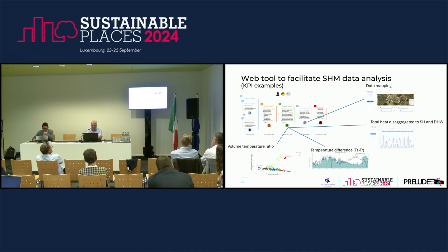We have worked with different tools. In the upper right corner, some data mapping to identify where in the system we might have high return temperatures, or which buildings are problematic. In the lower left corner, we have a picture of the volume-temperature ratio, because when systems fail, typically the return temperature increases, meaning a lower temperature difference, and then the volume flow increases. This is a typical signal that something is wrong.